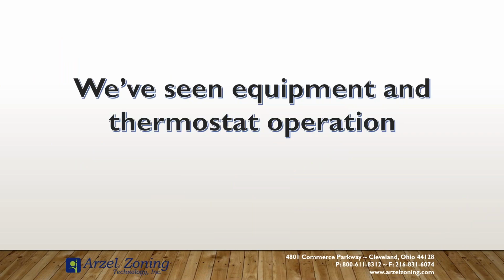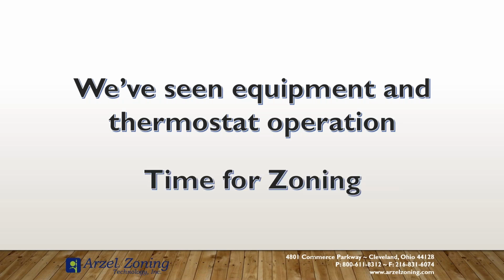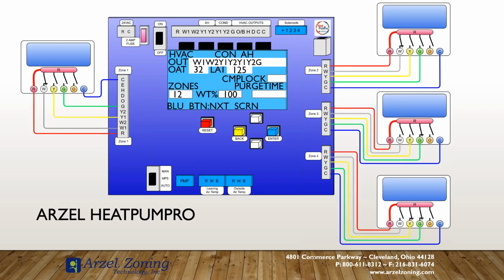So now that we've seen the equipment, now that we've seen how the thermostats operate, we need to add zoning to it. When we look at zoning, the zoning system takes multiple thermostats, applies a set of rules, and gives you your outputs. When we have the Arzel HeatPumpPro, all it needs is a W input, and it'll provide you with up to 4 stages of heat, 2 stages of cooling on the outputs based on your configuration. So if you have an all-electric system, a heat pump with 2-stage electric backup heat, the Heat Pump Pro will provide you with 4 stages of heat, starting with first and second stage condenser, moving to first and second stage of backup heat if necessary, based on your leaving air temperature.